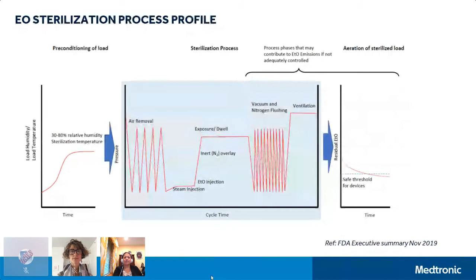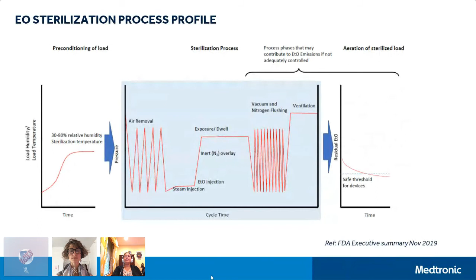The third step, and the most important step, is the aeration phase. This is where the product has completed the EO process but still has some absorbed residuals. During this phase, additional processing is performed to reduce the residual levels to the required standards. And this is a highly controlled and monitored phase, because if there is any shift in the process, you might see an increase in EO emissions.